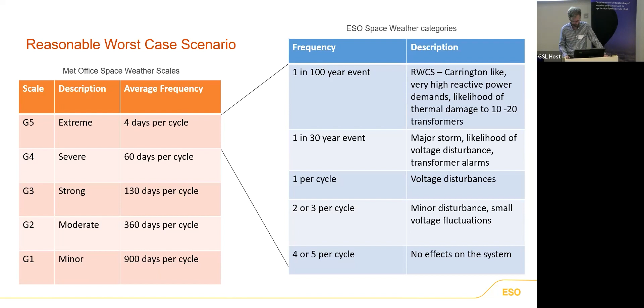Likelihood of thermal damage to 10 to 20 transformers. And that's a statistical value. If we were to lose transformers, it doesn't necessarily mean we'd lose demand, but I'll come on to that in a minute. In a 1 in 30-year event, classed as a major storm, a likelihood of voltage disturbance and transformer alarms, and 1 per cycle. We just see voltage disturbances on the network, 2 to 3, maybe some minor disturbance and small fluctuations, and in some cases might not actually see any effects. So it's quite a large range, obviously, within that G5 storm severity. Okay, so risk factors.